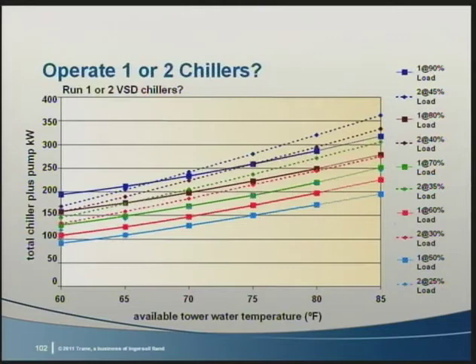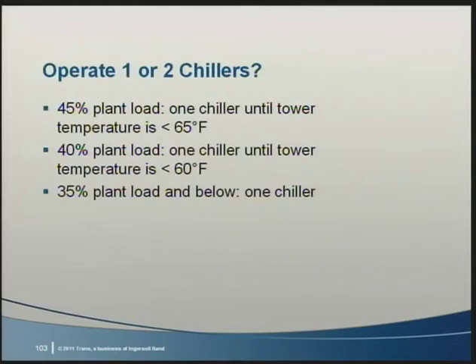So, if you want to operate more chillers than needed, don't do it until the tower leaving water temperature is below 65 degrees and plant load is 45% or less, or if the plant load is below 40% and the tower water is less than 60 degrees. And regardless of tower water temperature, turn a chiller off once the plant load is 35% or lower. I think you'll find very few hours when an extra chiller could be operated without wasting energy. Mick, I think it's time to dive further into coordinating chiller and tower control for reducing system energy.